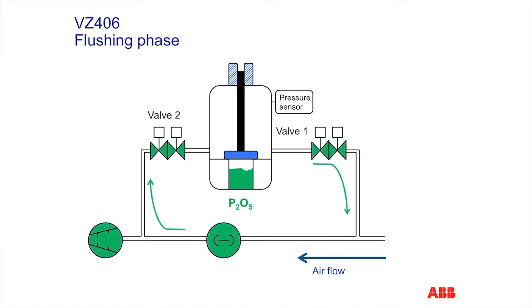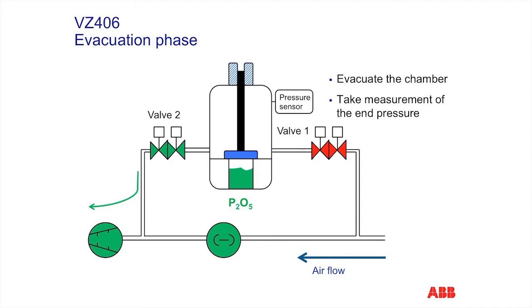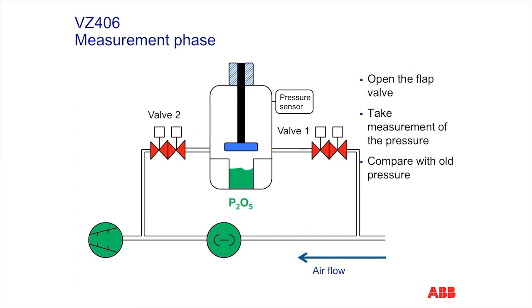The VZ406 passes a steady mixture of water vapor and air through it at the flushing stage. Then the valve is closed, and the chamber equilibrates to the final pressure that consists of the remaining air and the partial pressure of the water vapor in the effluent. At the time of measurement, the unit is sealed and the phosphorus pentoxide chamber opens and absorbs the water. The pressure gauge falls proportionately to the loss in water vapor pressure, and the computer is then able to calculate the concentration of water in grams per cubic meter at that point in time.